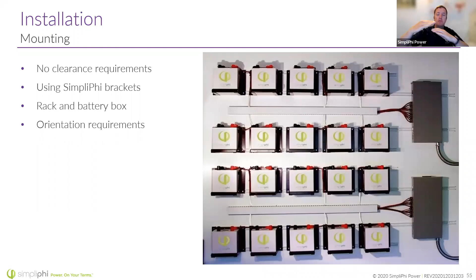When it comes to installation, there are no clearance requirements. You can put these batteries right up against each other, use some of our wall brackets like in the picture, or those Boss cabinets—Boss 12, Boss 6—that I already mentioned. I've seen a lot of great custom boxes built too, so we really leave it up to you. You can orient the batteries on their side or their face. The only orientation we don't want is upside down, with the terminals facing down, and we don't want them stacked on top of each other because the weight builds up too much.